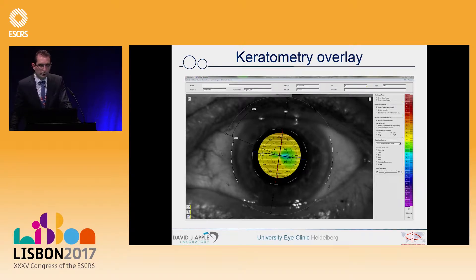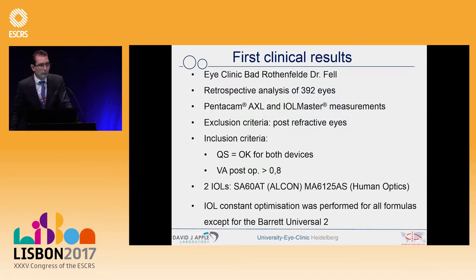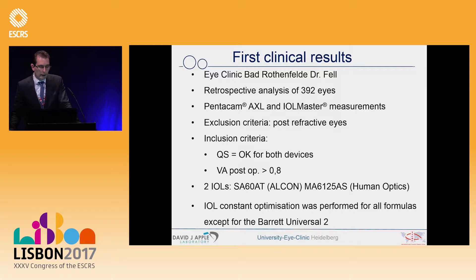This is a small glimpse into the near future — we will have a keratometry overlay working in the OR together with your OR microscope. We go into more detail for analysis of a retrospective case series of nearly 400 eyes from the Eye Clinic Bad Rothenfelde from Dr. Fell. They used the Pentacam AXL in the latest software version and compared measurements with the IOL Master 500. Exclusion criteria were all eyes after refractive surgery, and inclusion criteria required a quality score of OK for both devices.